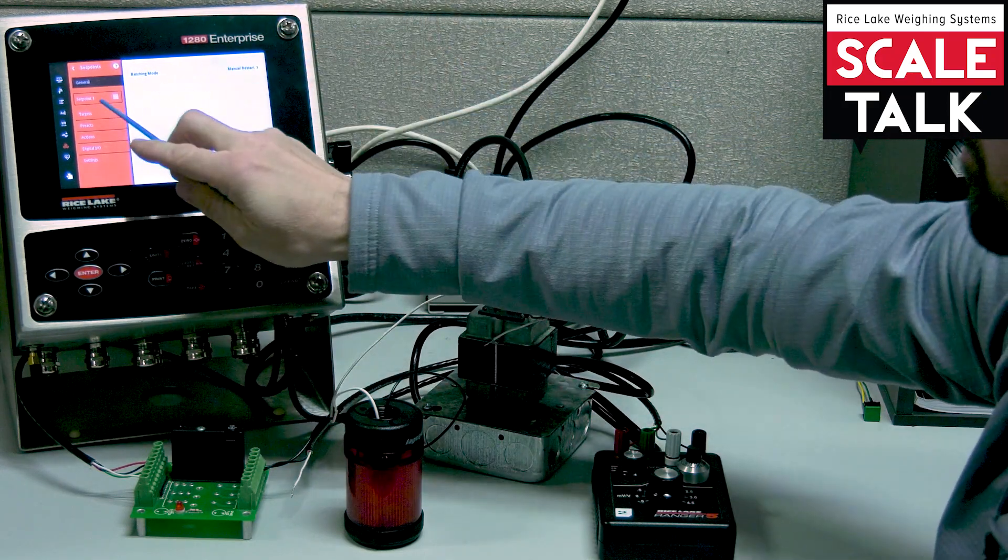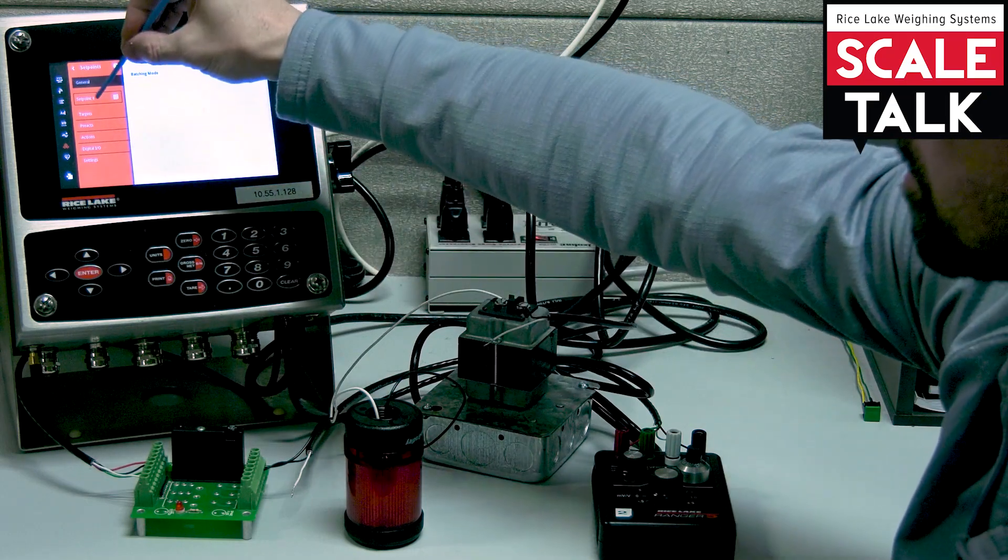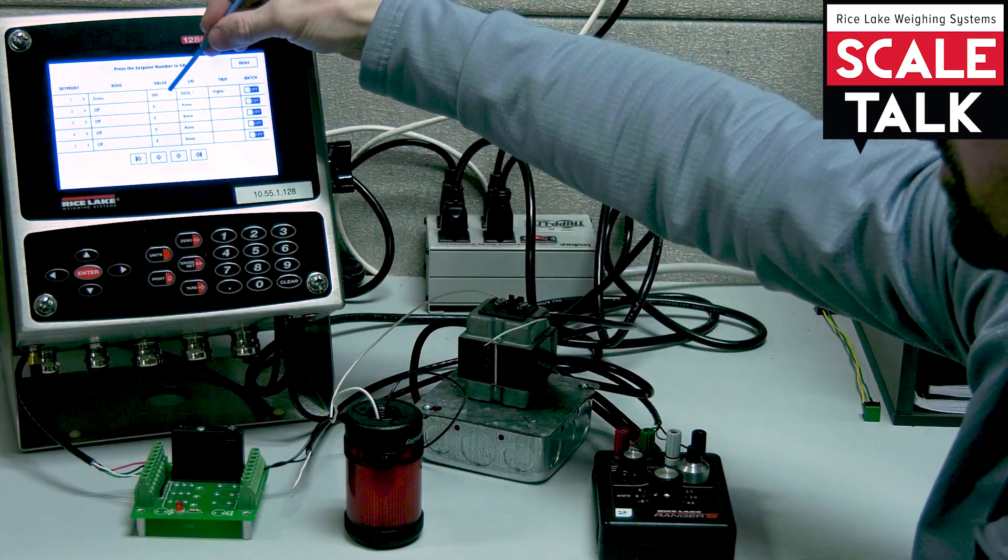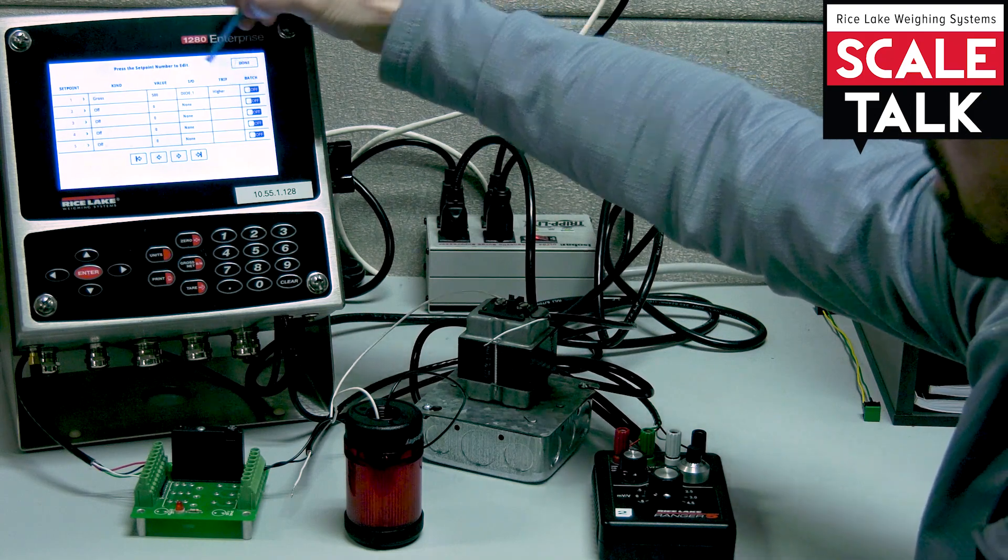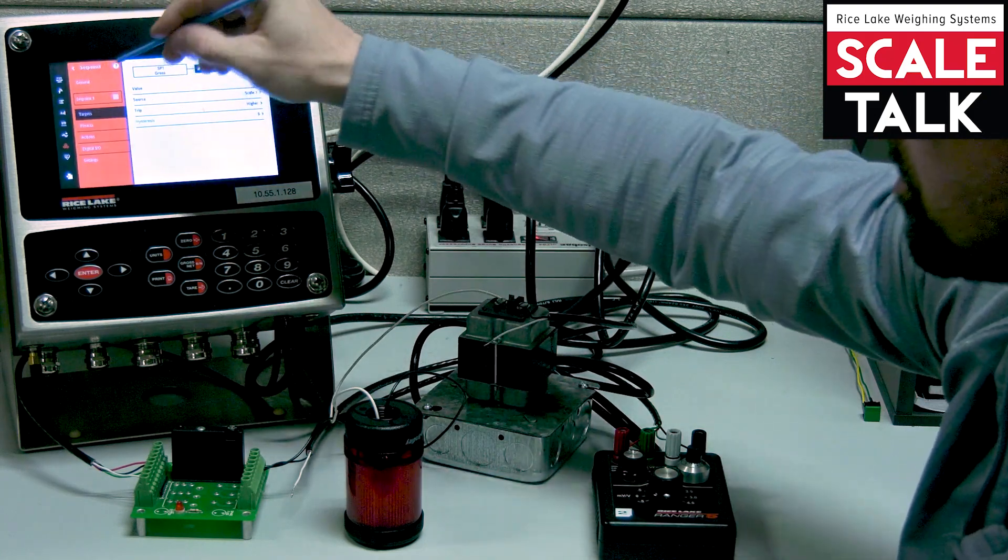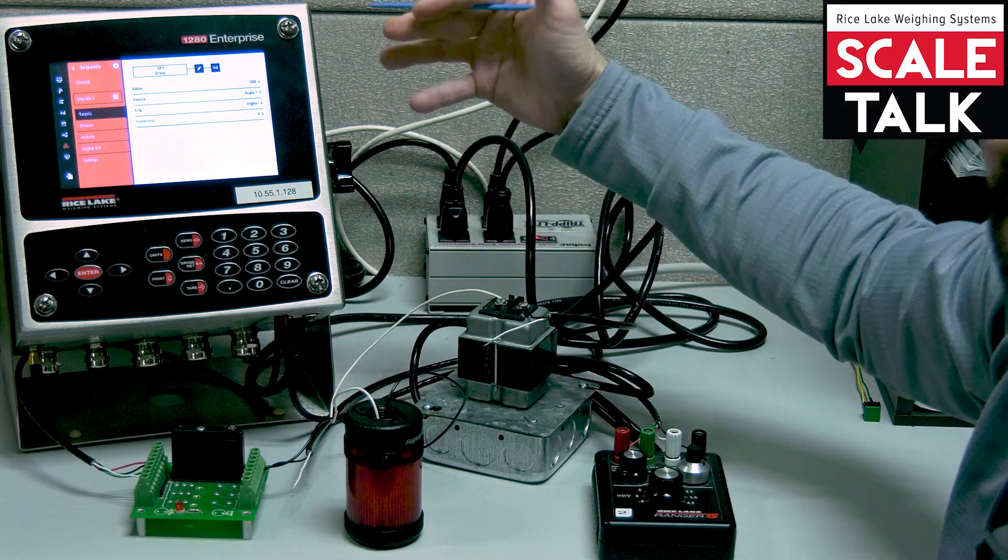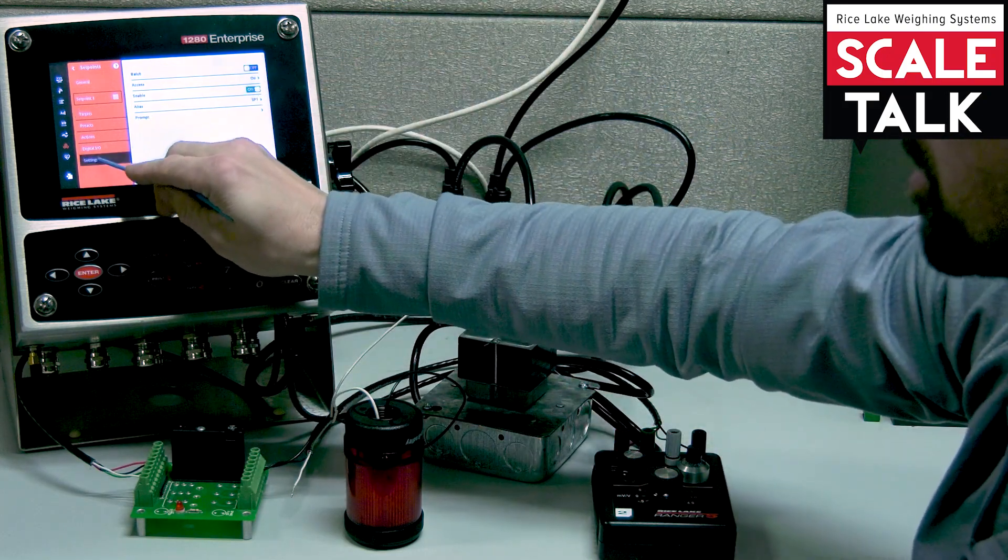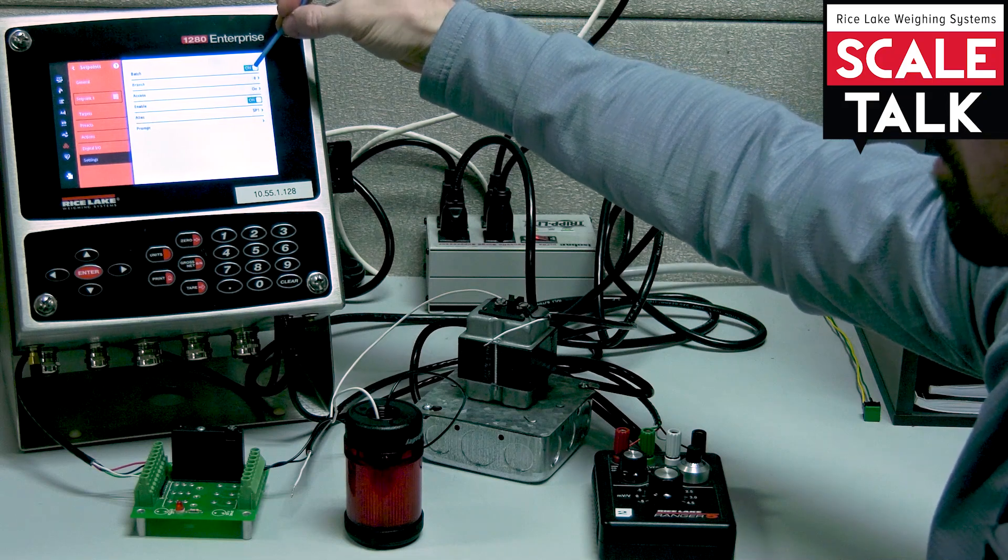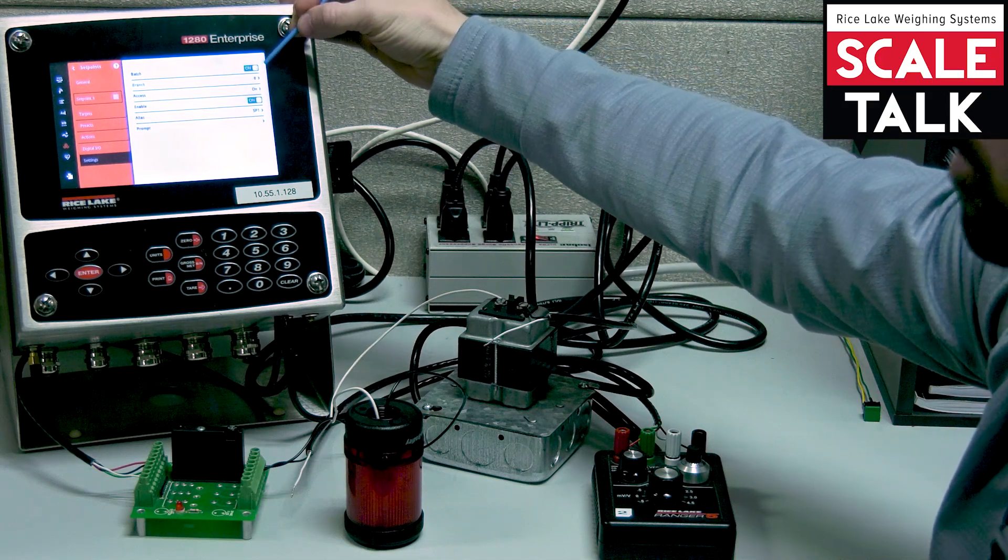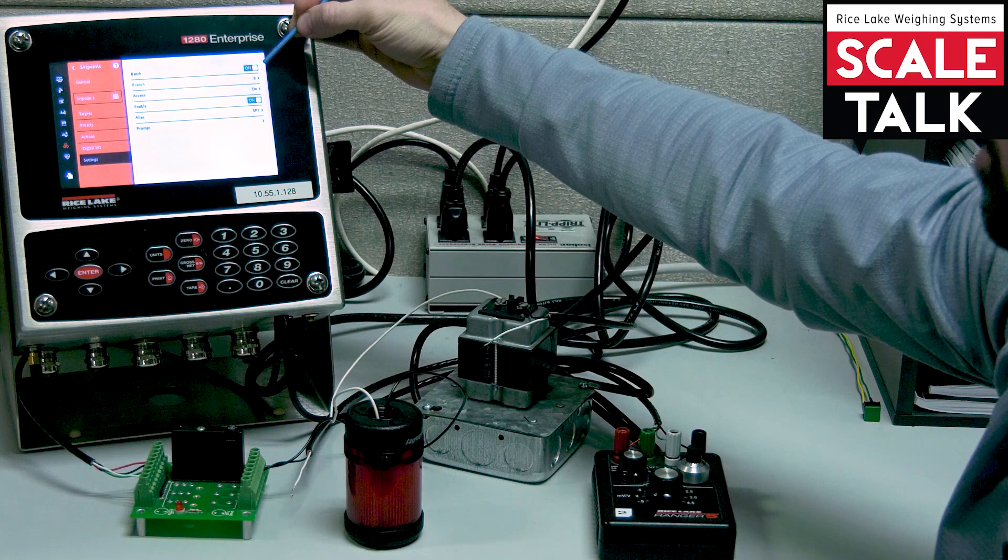For my first set point, I'm not going to change anything. We're going to leave this set at 500 pounds with digital I/O 1 to trip higher. But we're going to make sure that even though we've turned on the batching mode, we need to make sure in our settings that this particular set point is to be included in the routine. So we're going to turn that on here as well.